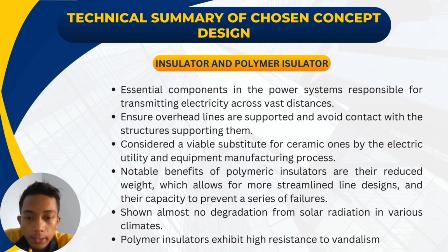Next is the proposed 2D and 3D drawing of the polymeric insulator. For our project, we propose a model of a 132 kilovolt polymeric insulator. The design features 9 sheds, comprising 5 smaller and 4 larger ones. The radius of the smaller shed is 100 millimeters, while the larger sheds have a radius of 110 millimeters. Each shed is inclined at a 45 degree angle.